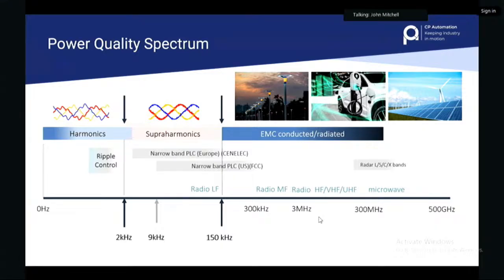And then we have EMC from a drive point of view, let's say RFI, which is conducted, and then you have radiated as well. But we're specifically talking about conducted here. And that's what an EMC filter is doing, for those of you familiar with drives, getting rid of the noise above 150 kilohertz. So supraharmonics sits in the middle, harmonics is down the end, and EMC is higher. And as you go down the spectrum, you need a lot more power and energy to get rid of that problem. As you go up the spectrum, a lot less energy to get rid of the problem.